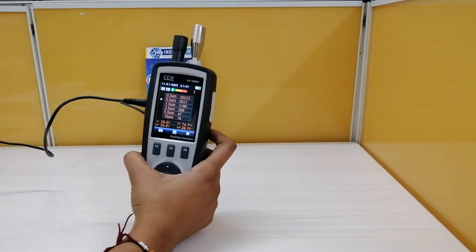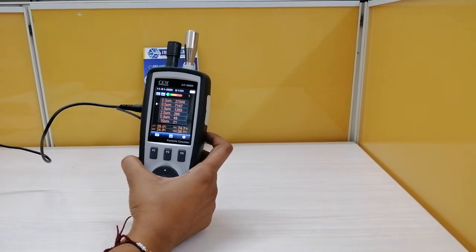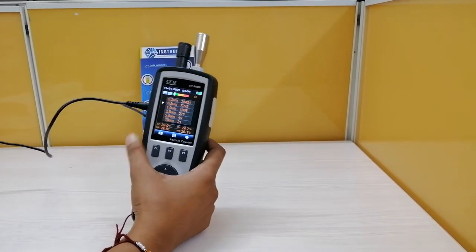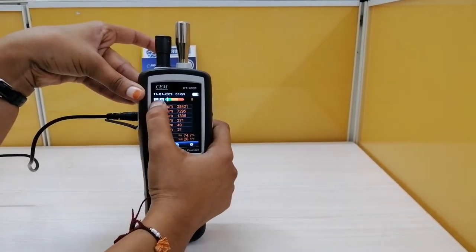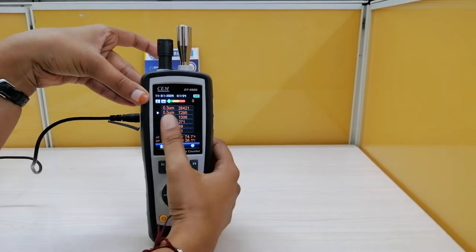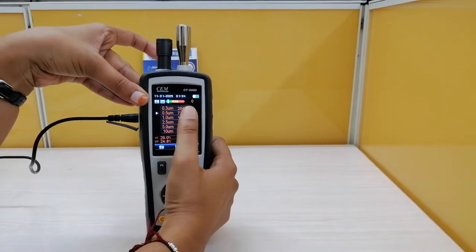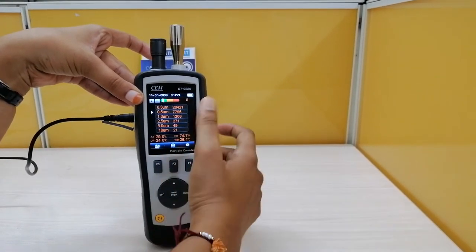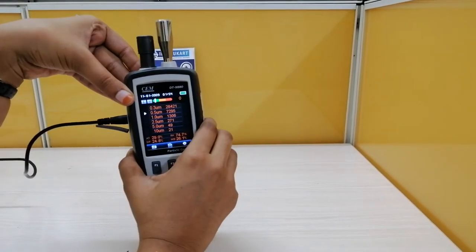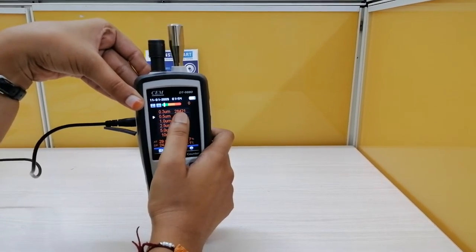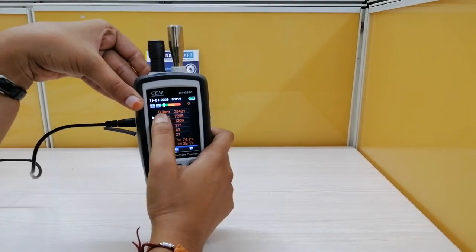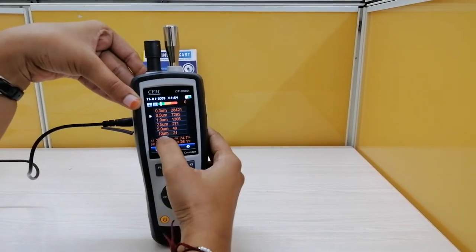This particle counter measures based on the sampling time and flow rate. You can see here this is in cumulative mode. This is the symbol of cumulative mode. And 0.3 microns shows 28,421. It means as the particle counter measured in cumulative mode, the 28,421 particles are there in between 0.3 to 10 microns.